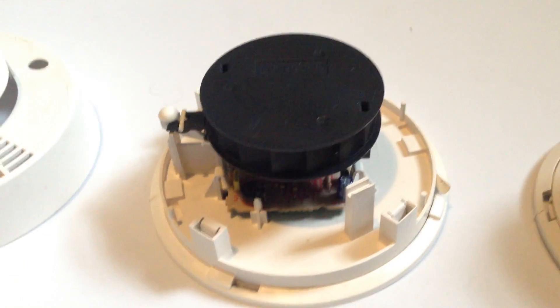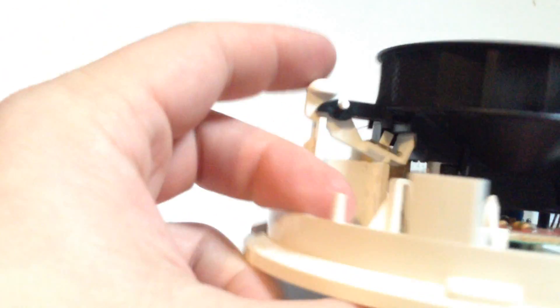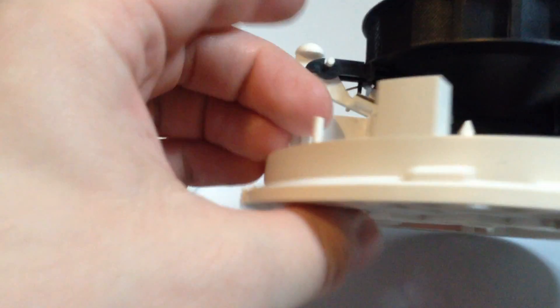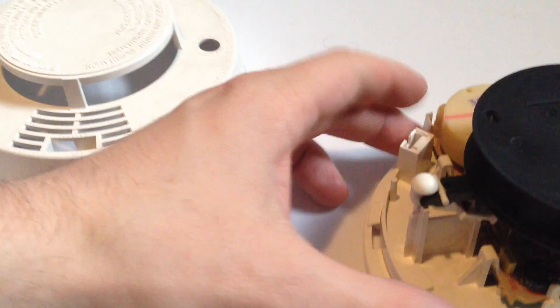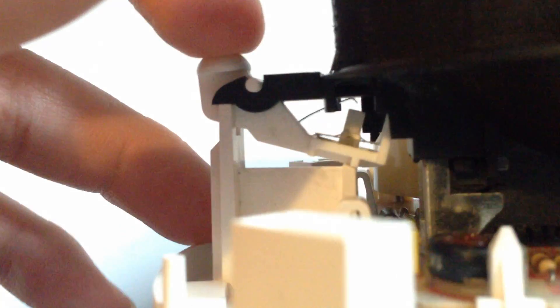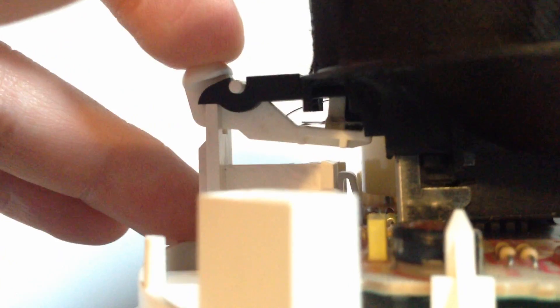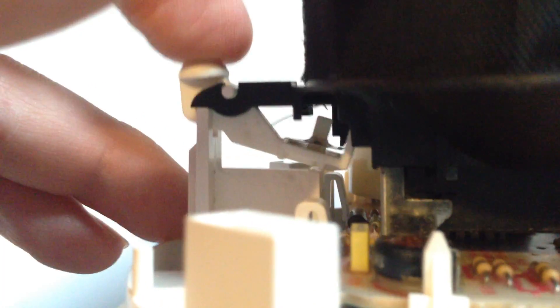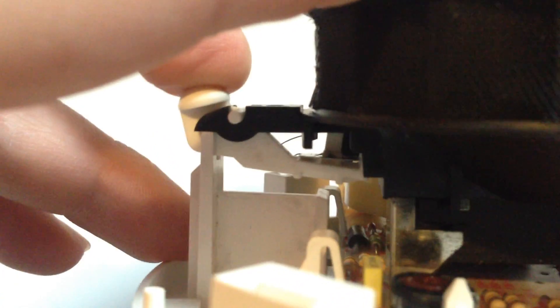Now, on the residential version, there is a lever connected to the test button. There's a hole for the test button, but there's a lever connected to the test button with a little piece of plastic. When you push up on it, it slides the piece of plastic into the detection chamber. Instead of just applying power to the circuit to make sure that the power supply works, it actually obscures the sensor slightly to make sure that the sensor is working.